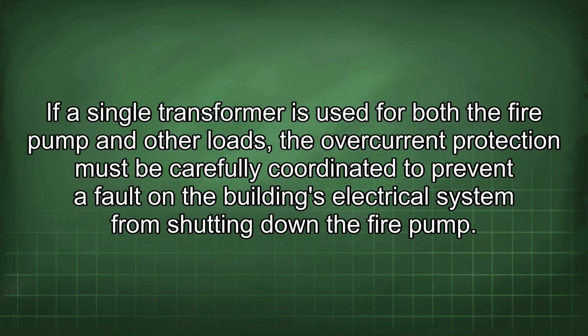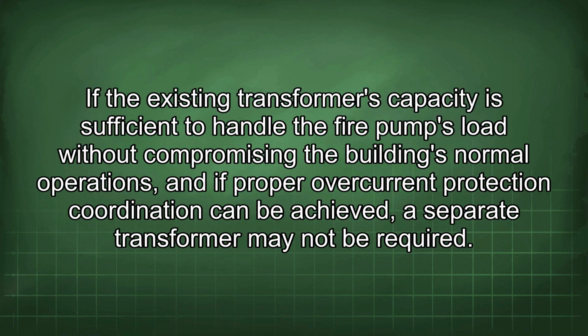If a single transformer is used for both the fire pump and other loads, the overcurrent protection must be carefully coordinated to prevent a fault in the building's electrical system from shutting down the fire pump. If the existing transformer's capacity is sufficient to handle the fire pump's load without compromising the building's normal operations, and if proper overcurrent protection coordination can be achieved, a separate transformer may not be required.